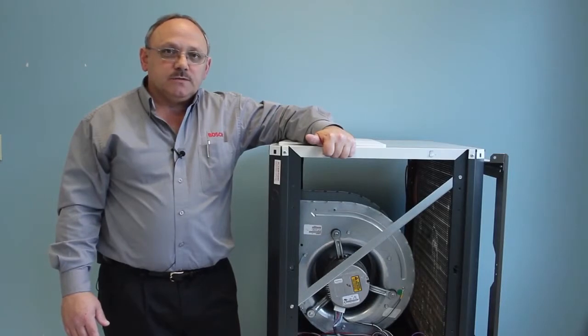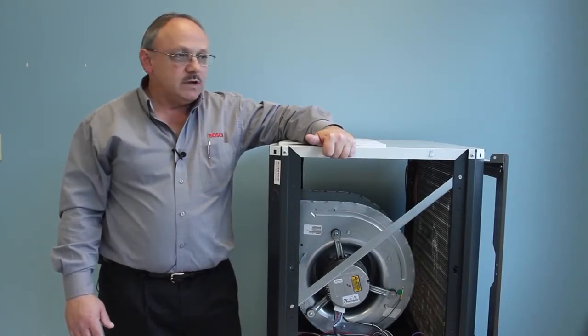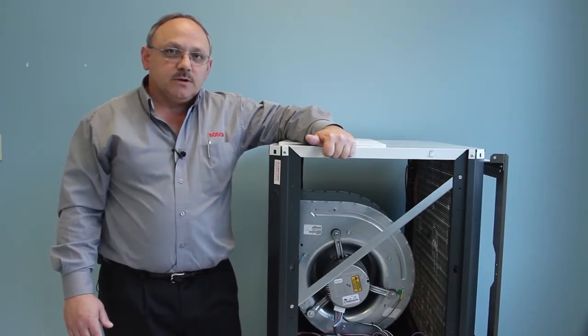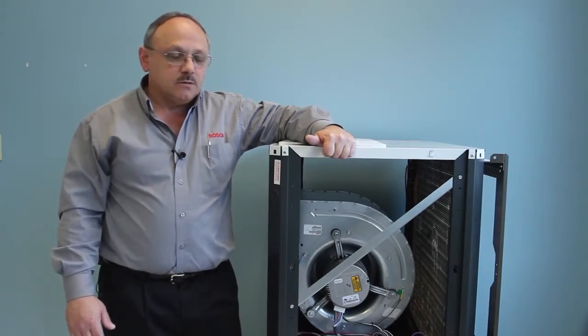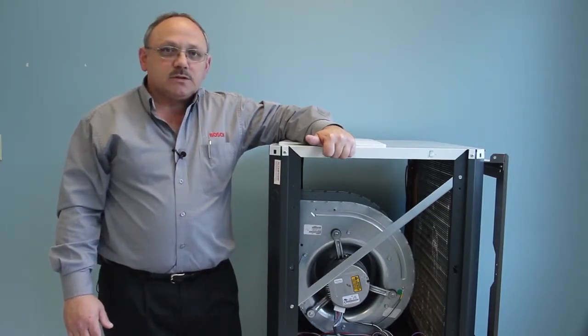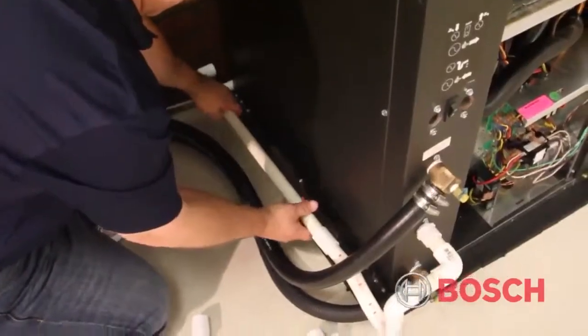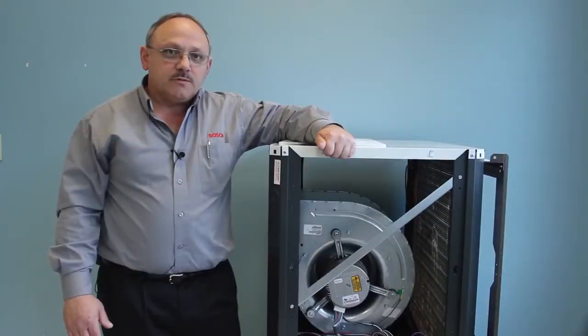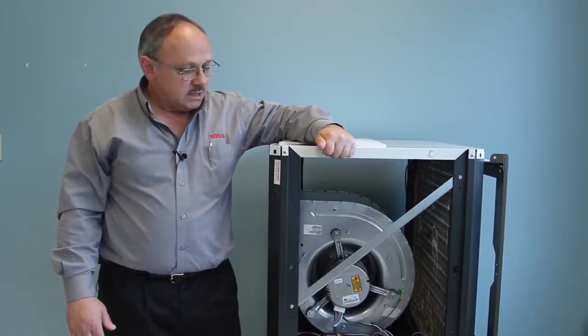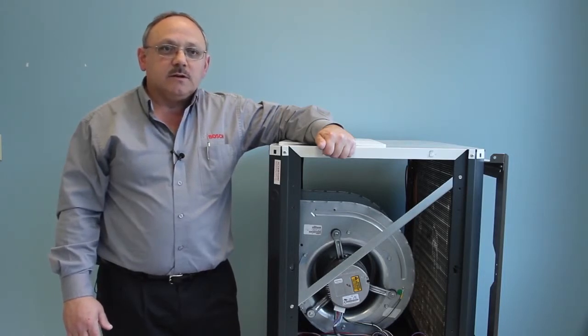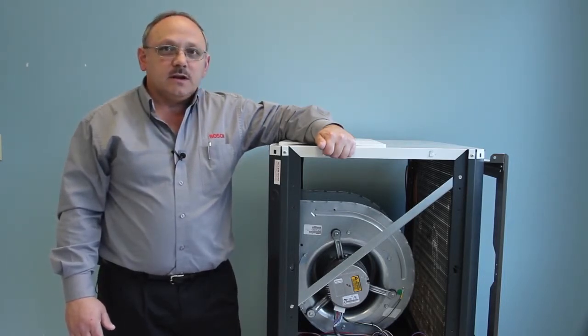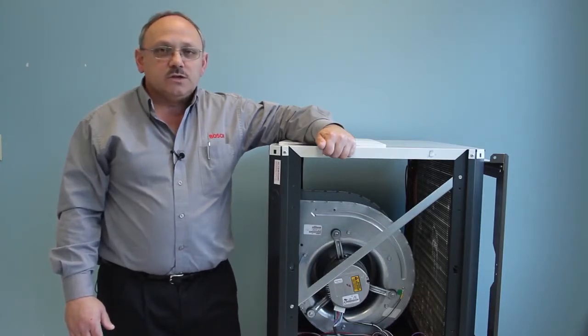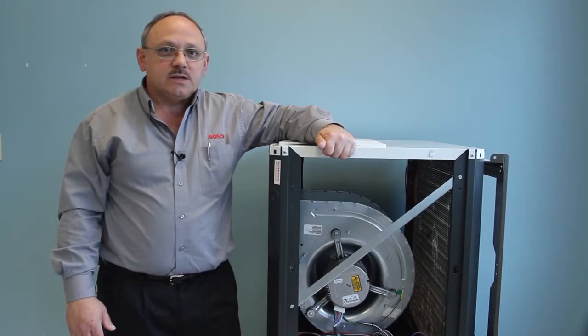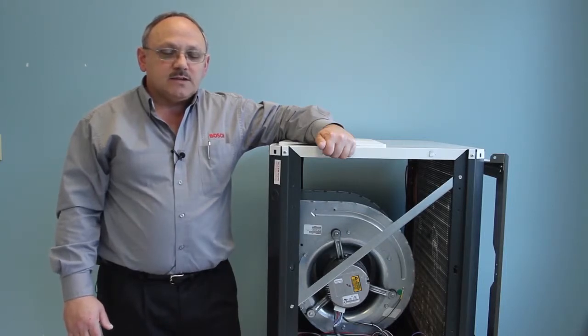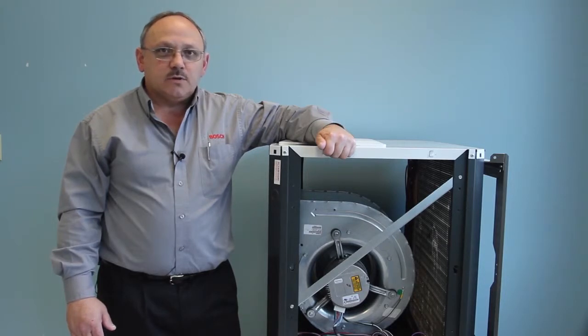Once you've field converted your unit to fit your application and you've set it in place and made your duct connections, the next step would be to run your electrical connections and your water connections to the equipment. We've highlighted all of those processes in our TA series installation video, and they'll be very similar to what you will do with the SM model, so we will not repeat that in this video. Knockouts are provided for both high and low voltage connections to the equipment, and the water connections we looked at earlier in this video are located underneath the return air connection on the side of the unit. Once you've made your electrical and your water connections to the unit, the next step is setting up all of the boards. And then the steps after that include startup and commissioning of the product.